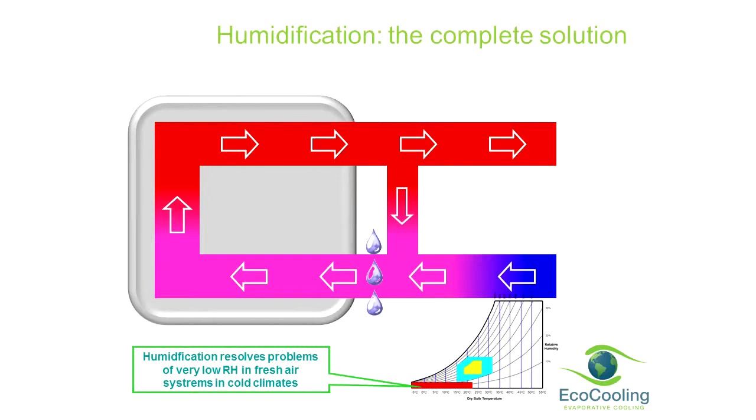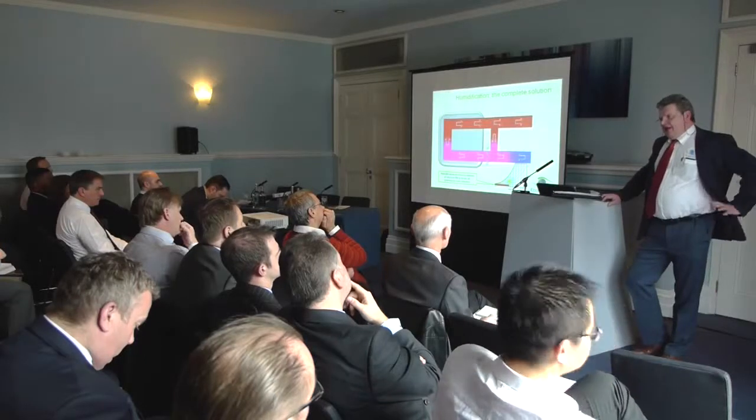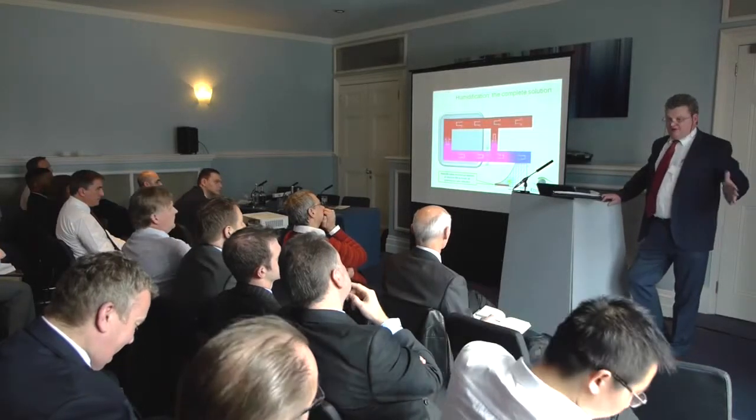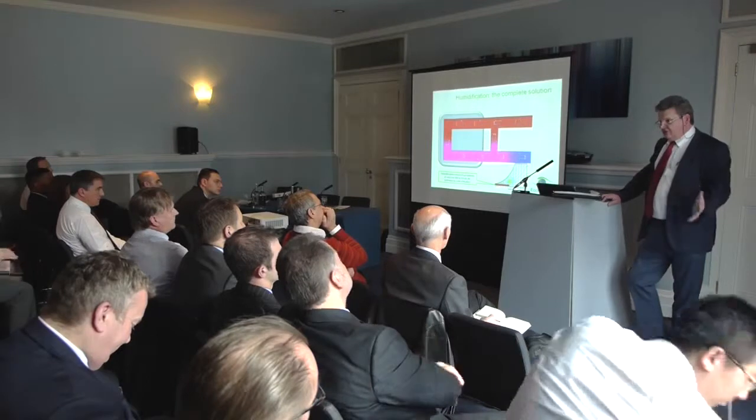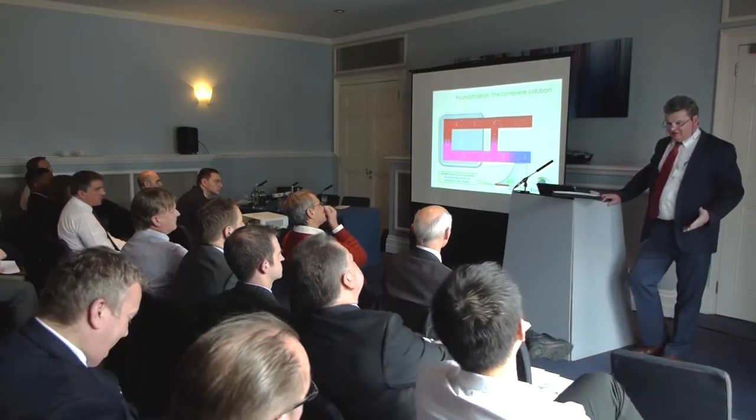I can't show you the actual way that the system up there is going to work, because it's subject to a patent application. But one problem you do get using fresh air in the far north is really low humidities in your data centre. ASHRAE says equipment now is very resilient to low relative humidities and static electricity problems. No, we aren't completely convinced about this. So people are looking for avoiding low humidities.